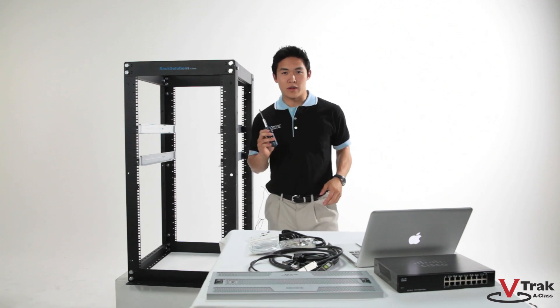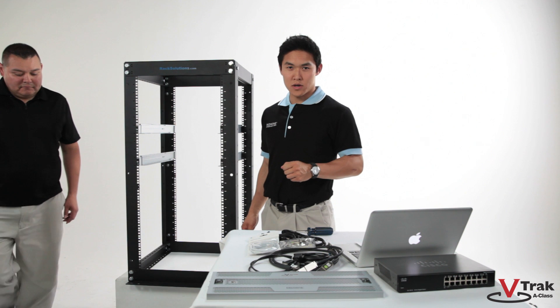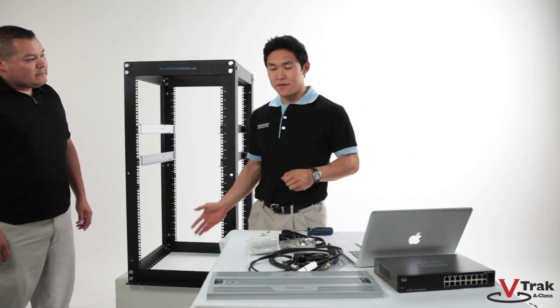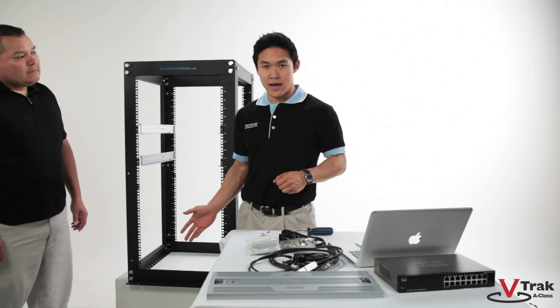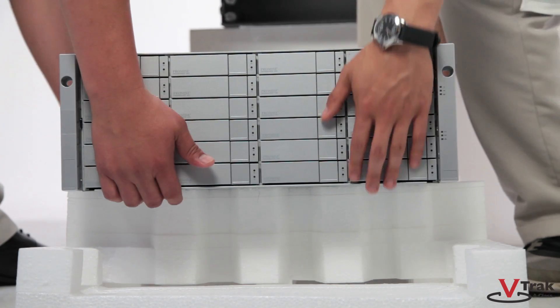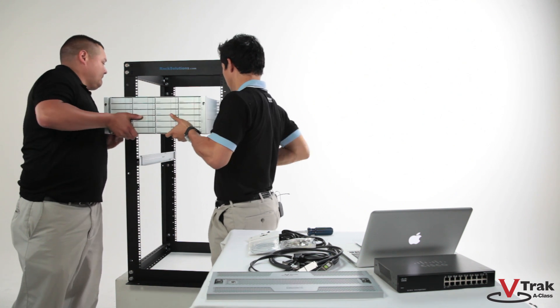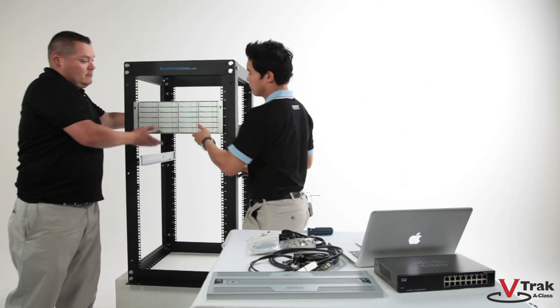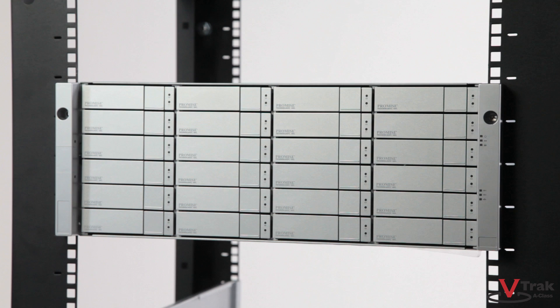Now that the rails are in place, we can rack the VTrak A-Class. This requires two people — you can get a coworker or a friend. When lifting the VTrak A-Class, do not lift it by the handles, but lift it by the bottom, front and center. Now secure the VTrak A-Class with its two front mounting screws and place the security cover over the front.